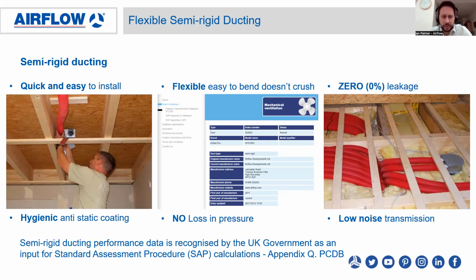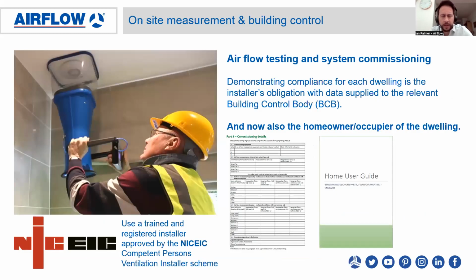So semi-rigid ducting performance data is recognised by the UK government as an input for SAP calculations, Appendix Q, and again this system can be found on the PCDB database. Just search for semi-rigid ducting. Finishing here with airflow testing and system commissioning. Demonstrating compliance for each dwelling is the installer's obligation, with data supplied to the relevant building control body. And now also, as we mentioned earlier in the presentation, the homeowner, occupier of the dwelling, must be provided with commissioning details and a home user guide for their ventilation system.